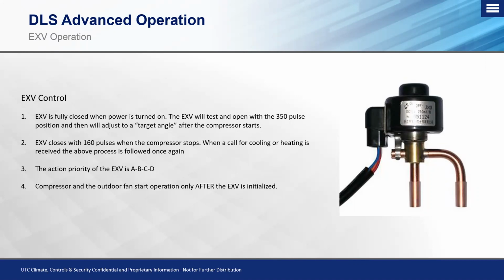Okay, you have to understand in the heating mode that these do not close 100%, and that ultimately stems back to circulation of oil back to the compressor because we have multiple ports and we could pipe great distances with the ductless split system, so we don't want oil trapped out in the lines. We need to get it back to where it matters, which is at the compressor.